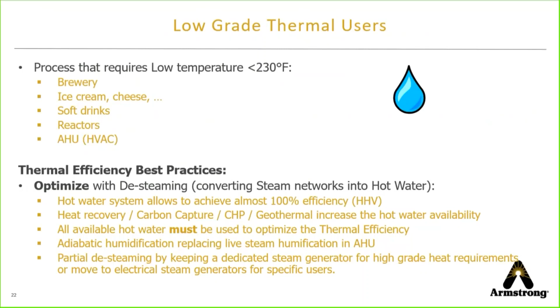De-steaming low-grade heat, we're going to look at heat source, heat sink analysis, the physical time, location, the level of temperature, the amount of heat we have, where that sits in the plant. Are we generating the heat we need, or is it waste heat we have but need to use 1,000 feet away? How are we going to transport it? How are we going to store it? What does that look like from a piping network? What makes more sense for one area versus the other?